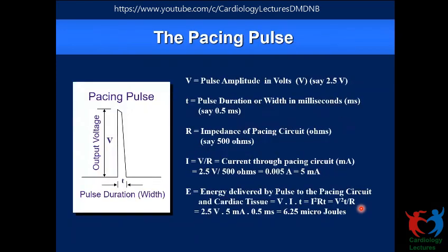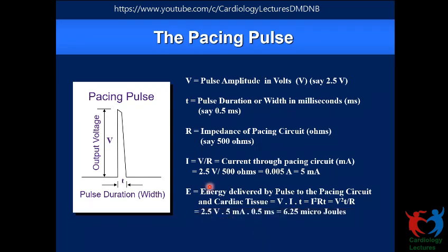Why I am emphasizing this so much is that there are occasions when we want to increase the output, probably because of a higher threshold that the patient reports with. Yes, we need to be safe for the patient, but just blindly increasing the output to 2 times what exists might result in an energy outgo of 4 times. Instead, one option could be to check the threshold one more time at a higher pulse width, so we might get a lower threshold. Assume the threshold was 2.5 volts. If we increase the pulse width to 0.8 millisecond and then check the threshold, it is likely to be below 2.5. At that pulse duration, we can increase the amplitude reasonably so that the total energy outgo is controlled, and it's not as high as when it is doubled at 5 volts.